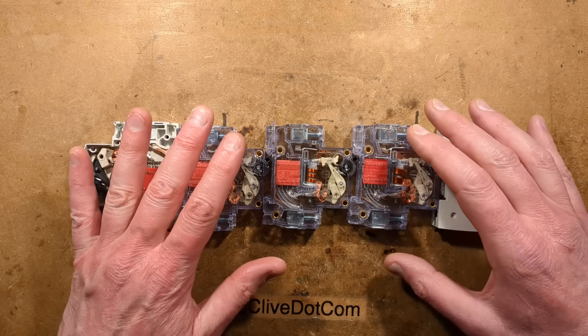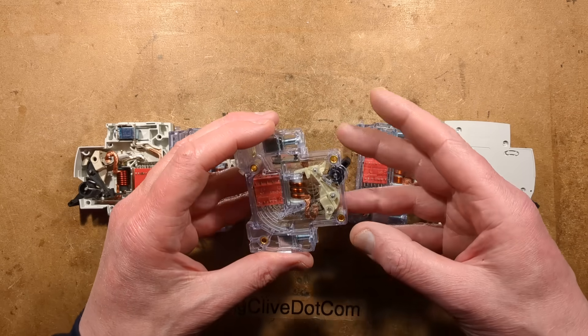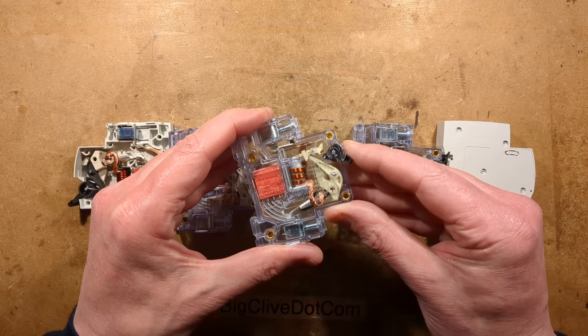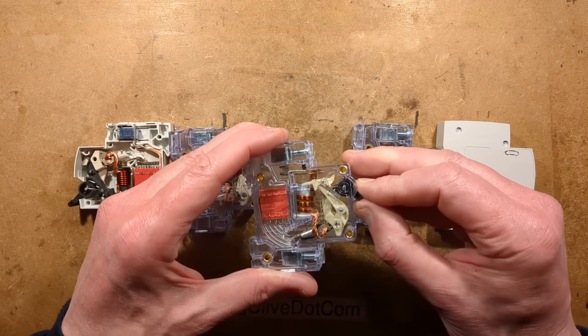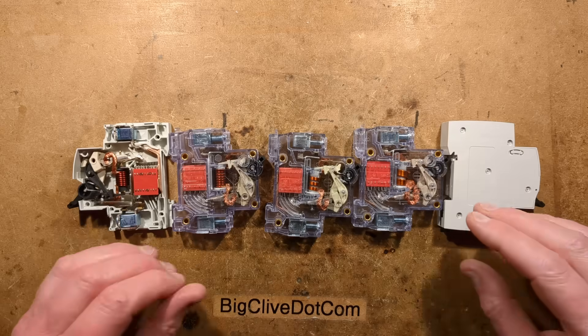Let's take a look at some circuit breakers, the way they operate and why, contrary to some of the images you see on the internet, you can't just jam the switch in the on position and hope that it's not going to trip. It will trip inside and I'll demonstrate that later on and I'll show you the full tripping mechanism.